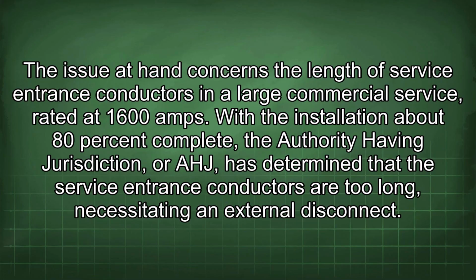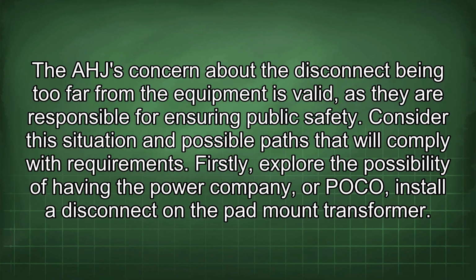The issue at hand concerns the length of service entrance conductors in a large commercial service, rated at 1600 amps. With the installation about 80% complete, the authority having jurisdiction, or AHJ, has determined that the service entrance conductors are too long, necessitating an external disconnect. The AHJ's concern about the disconnect being too far from the equipment is valid, as they are responsible for ensuring public safety. Consider this situation and possible paths that will comply with requirements.